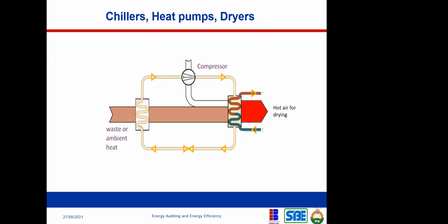So it collects the normal air that you have in your environment, which sometimes can be at maybe 30 degrees centigrade or 35 degrees centigrade. It compresses it and the air becomes hot, maybe 80 degrees centigrade or 90, depending on the capacity of the compressor. Then you pass that hot air through water. Water then absorbs it and the water becomes hot. That's what a heat pump does, right? And that's what this diagram is trying to illustrate.